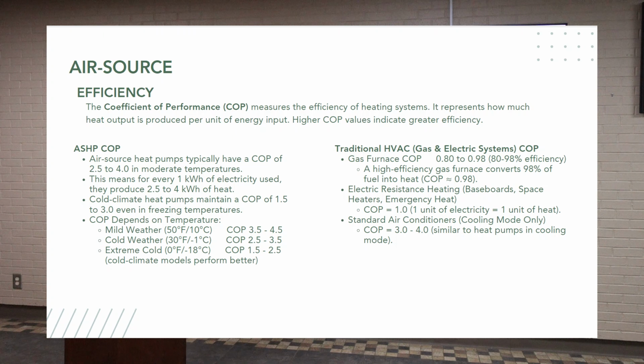We talk about efficiencies when we talk about heat pumps, and there is what they call a coefficient of performance, which is essentially efficiency: what the output is divided by what the input is. How efficient are these things operating? On an air source, you usually run anywhere from a 2.5 to a 4 in those numbers. That means for 1 kilowatt hour of electricity used, they can produce anywhere from 2.5 to 4 kilowatts of heat.